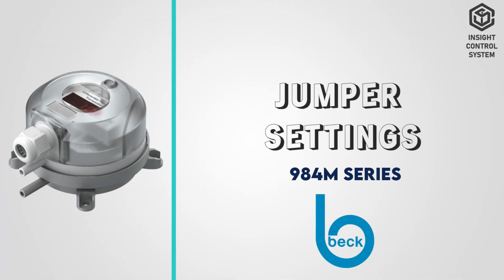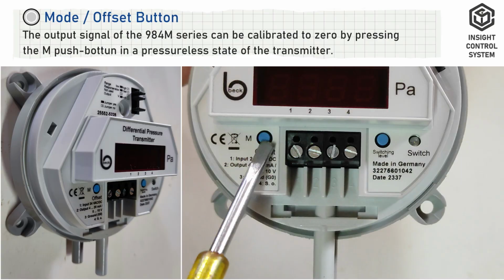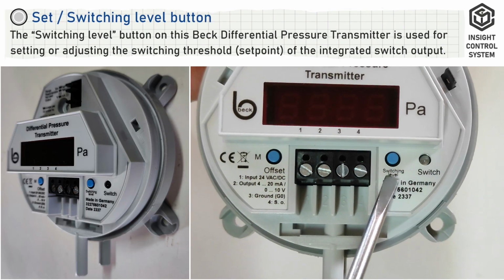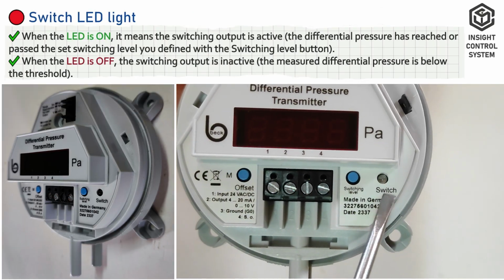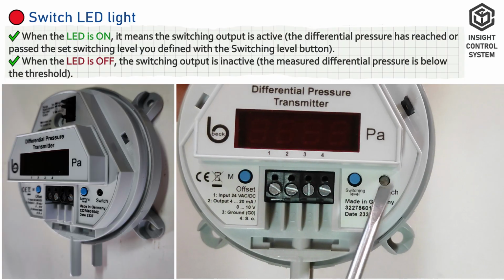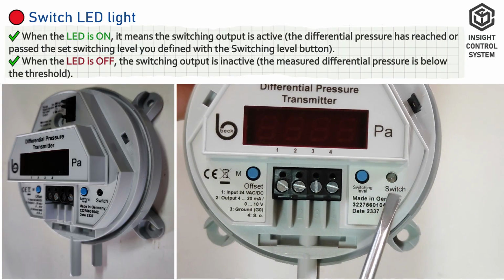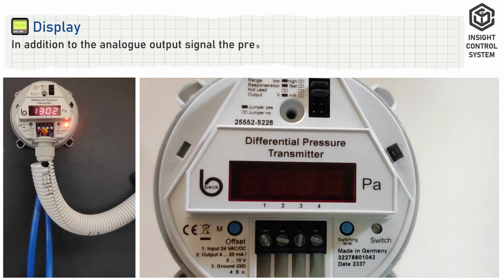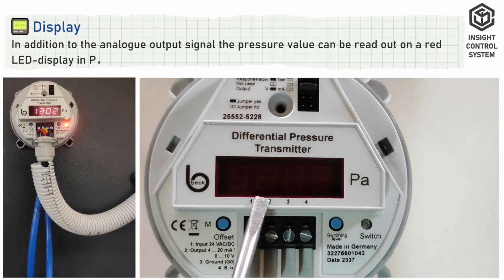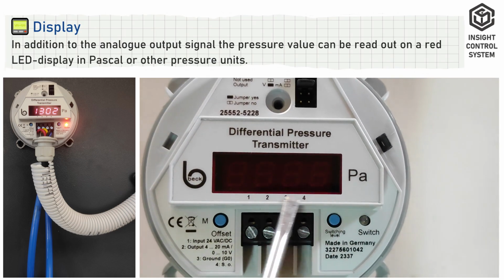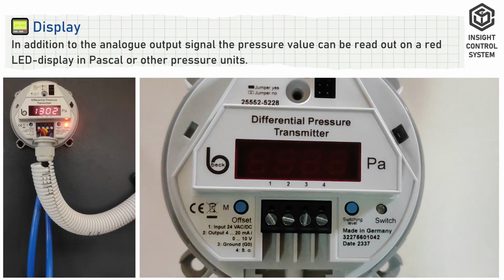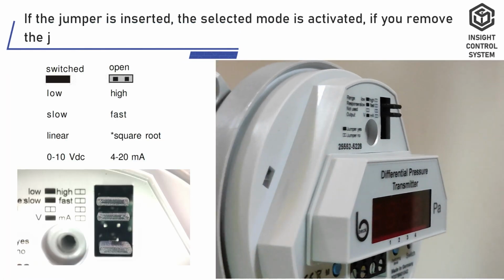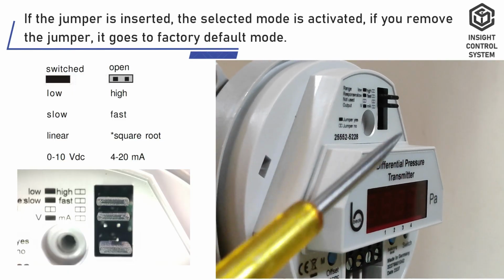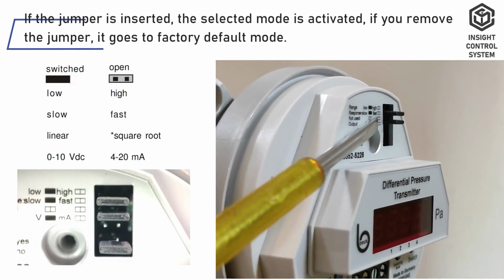Jumper settings: this is mode or offset button. This is set or switching level button. This is switching LED light. The LED lights up as soon as the defined pressure is reached or exceeded. This is LED display. The pressure value can be read out on a red LED display in Pascal or other pressure units. If the jumper is inserted, the selected mode is activated. If you remove the jumper, it goes to factory default mode.